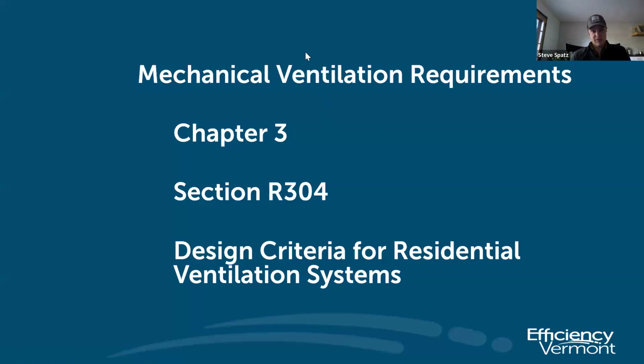So that was all kind of the lead into the actual mechanical ventilation requirements, because I do think it's important to take into context that there is passive control that we want to maintain for loading building assemblies with moisture. But when it comes down to it, the mechanical system that's actually going to be operating and keeping things in check is a critical component, so that those passive parts of the building are not stressed and can perform as effectively as possible.